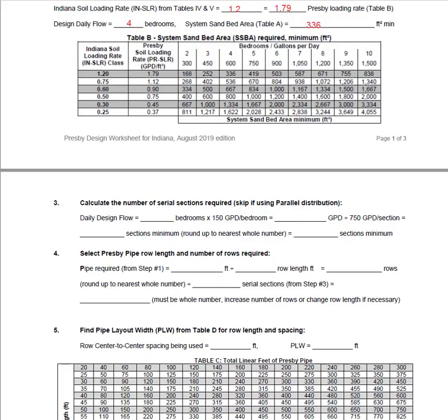We will now move on to step number three, which is only applicable if you are using serial distribution. If you are using parallel distribution you can skip this step. Because we are using serial distribution, we're going to continue. Our daily design flow is calculated using the number of bedrooms — four — and at 150 gallons per day per bedroom, we wind up with 600 gallons per day total. Because the maximum flow for each section is 750 gallons per day, we divide 600 by 750, bringing us to 0.8. Rounding up to the nearest whole number, our minimum number of sections is one. If this had been a six-bedroom system, we would have needed at least two serial sections.